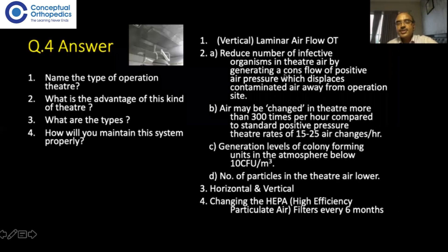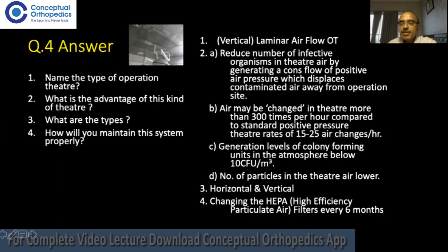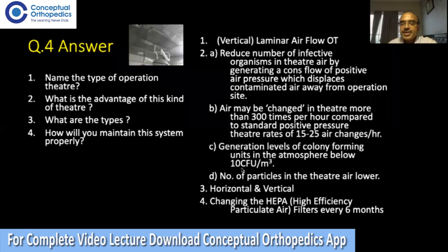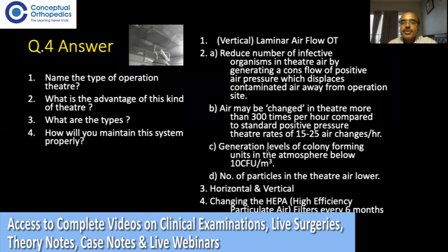The advantages of laminar airflow are: first, it reduces the number of infective organisms in theater air by generating a continuous flow of positive air pressure, which displaces contaminated air away from the operation site. Second, air is changed more than 300 times per hour, compared to standard positive pressure at 15–25 air changes per hour. Third, colony-forming units in the atmosphere are kept below 10 per cubic meter — corresponding to Class 10 laminar airflow classification. Fourth, the number of particles in the theater is lower.